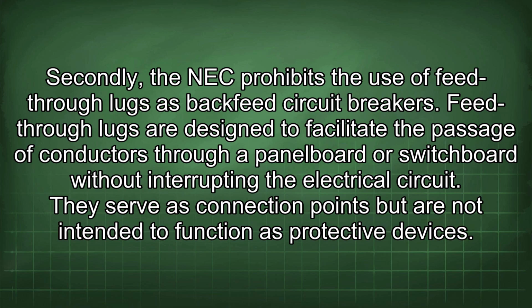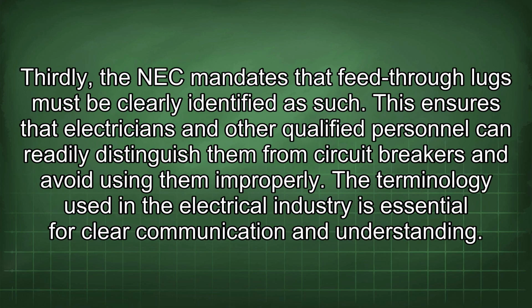Secondly, the NEC prohibits the use of feed-through lugs as backfeed circuit breakers. Feed-through lugs are designed to facilitate the passage of conductors through a panel board or switchboard without interrupting the electrical circuit. They serve as connection points but are not intended to function as protective devices. Thirdly, the NEC mandates that feed-through lugs must be clearly identified as such. This ensures that electricians and other qualified personnel can readily distinguish them from circuit breakers and avoid using them improperly.